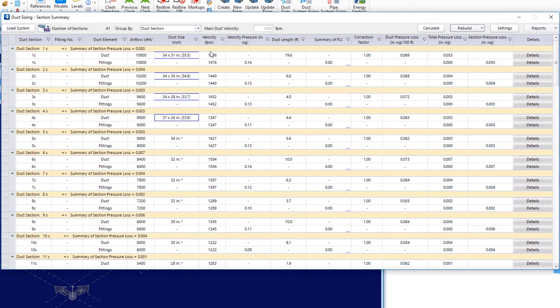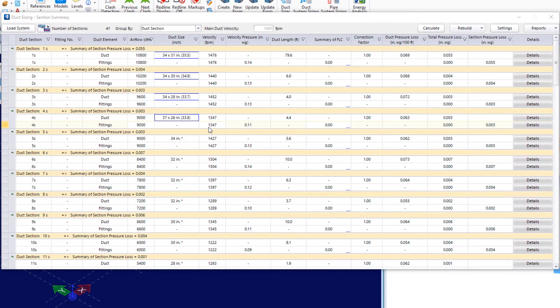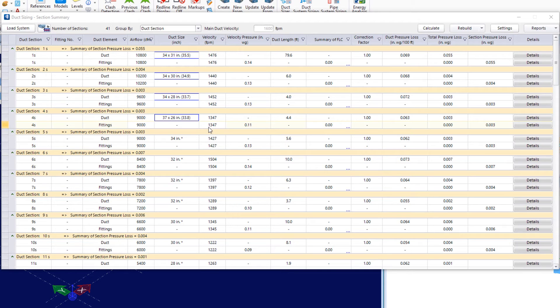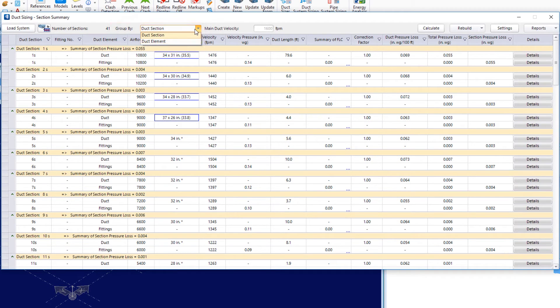So, now I see that I don't have any of those red indicators for those duct sections, whether it's for the duct size or the velocity. Now, the next thing I'll do is lock the values of duct sizes for the rectangular and round duct sizes to minimize the number of transition pieces before I promote the single line to 3D. Now, in the duct section summary, we have this group by option. So, we can look at it either by duct section or by duct element.